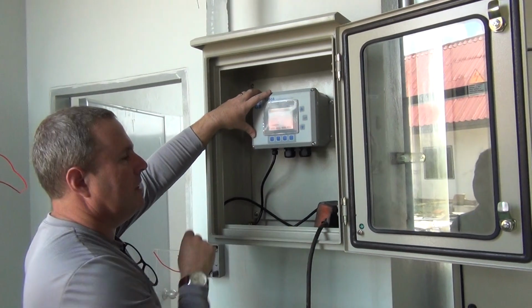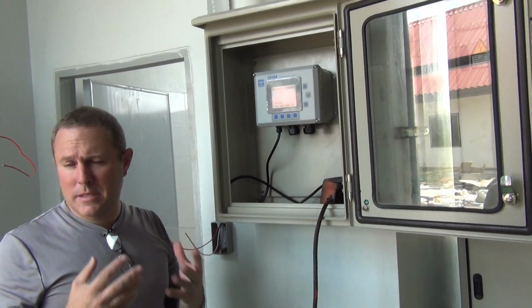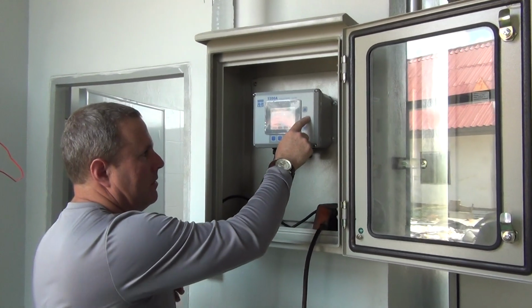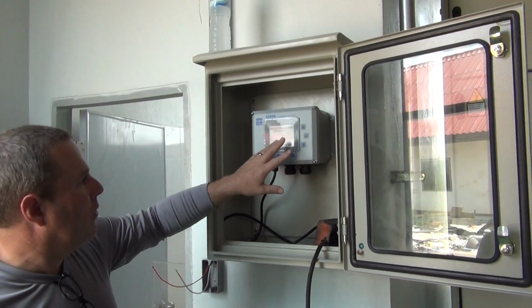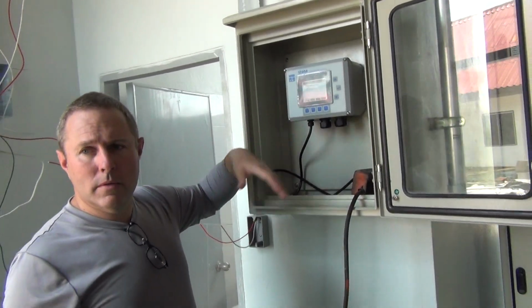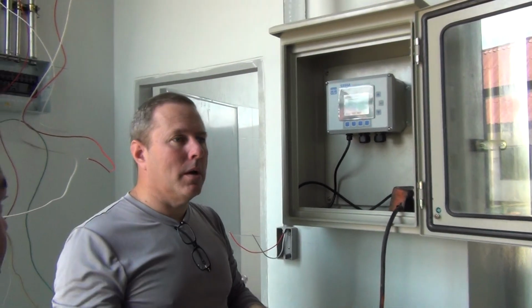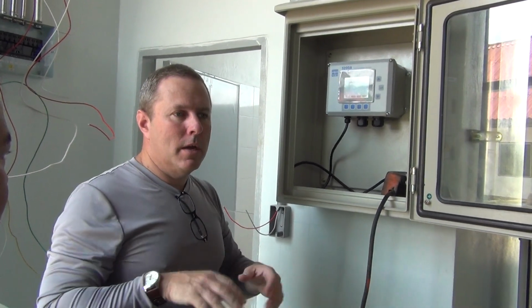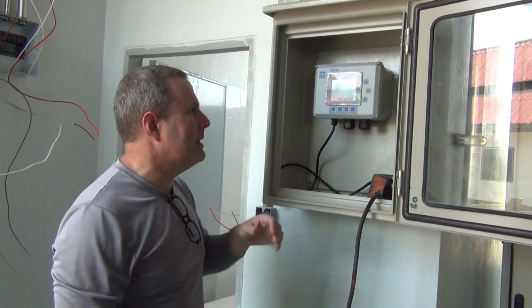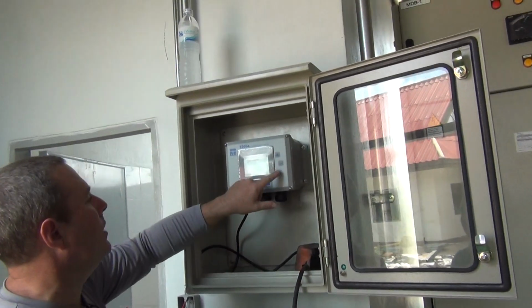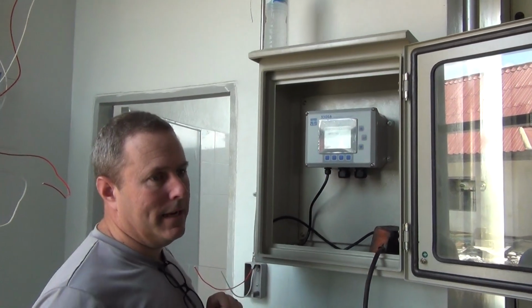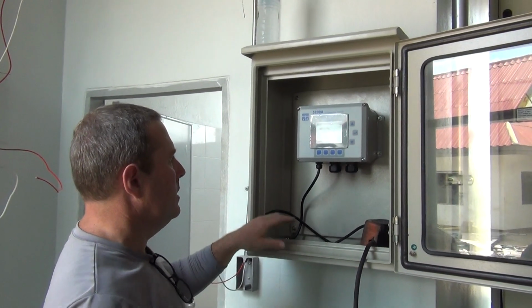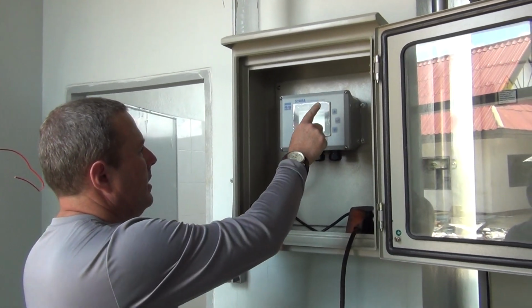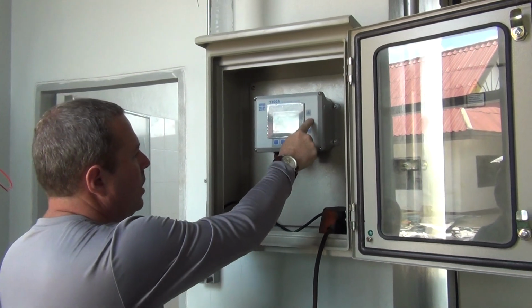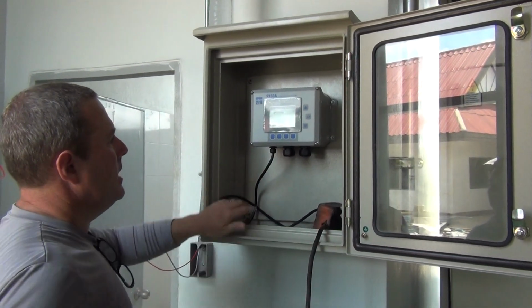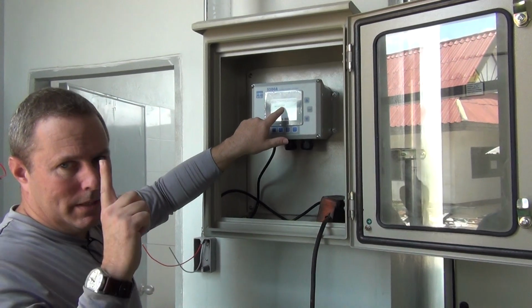the next one is general alarm. And this is what's going to set the parameters for what triggers the buzzer and what would cause it to send the email message to the cell phones and SMS messages. And so we have alarm hold off time, 15 seconds. We're going to change this, and we're going to say alarm hold off time 1 and save. Now it says alarm hold time 1 second.